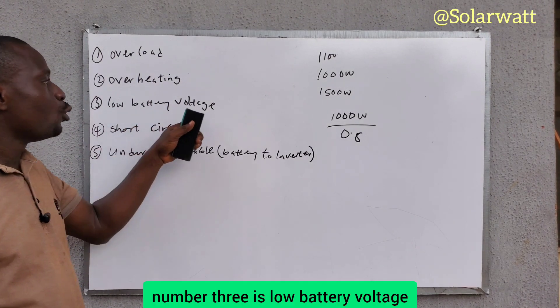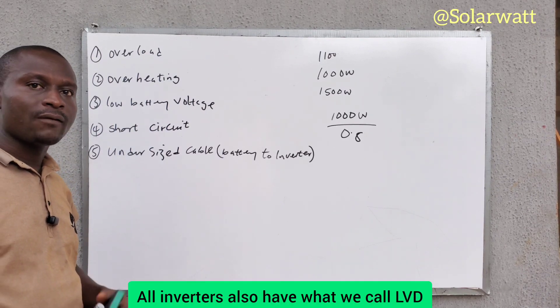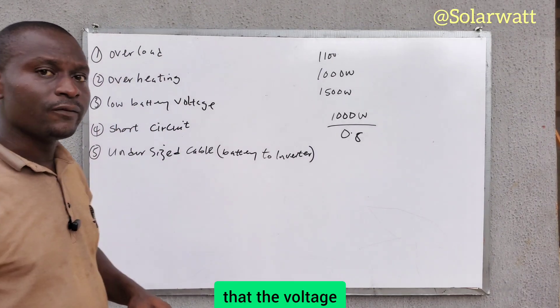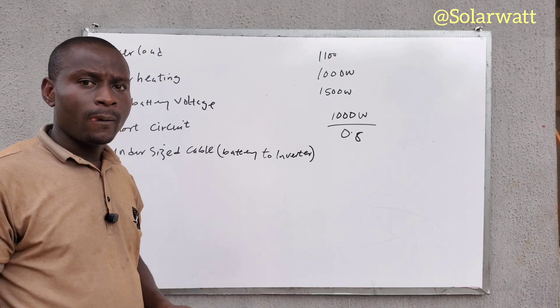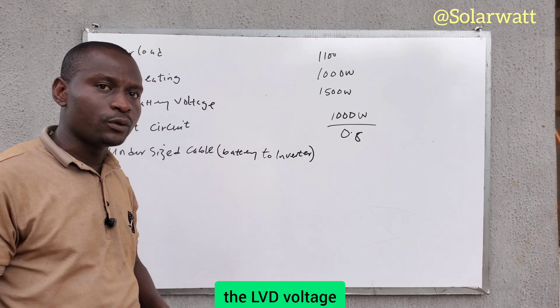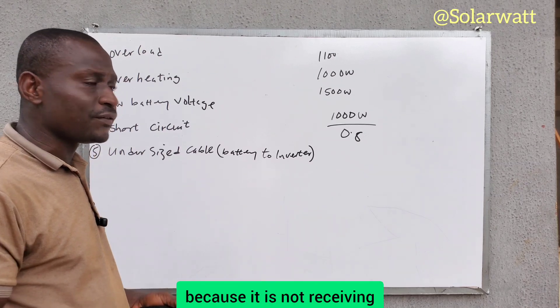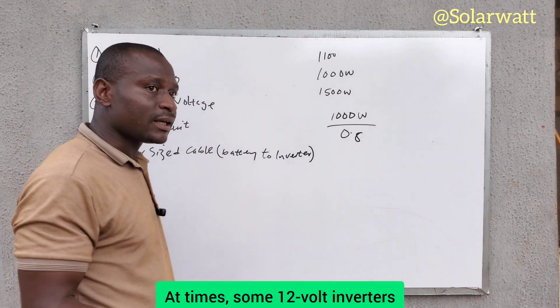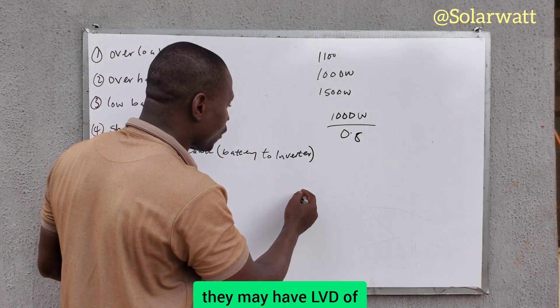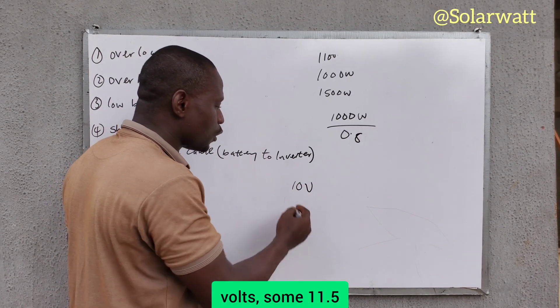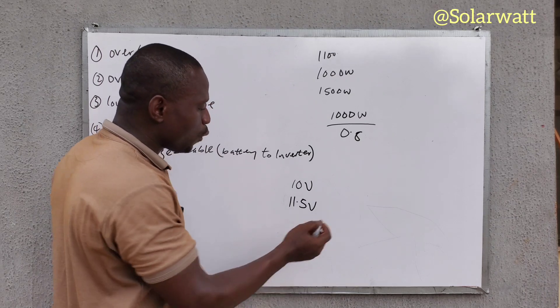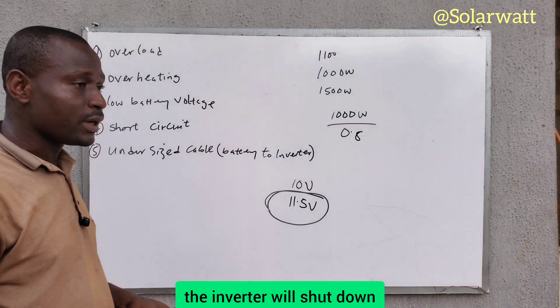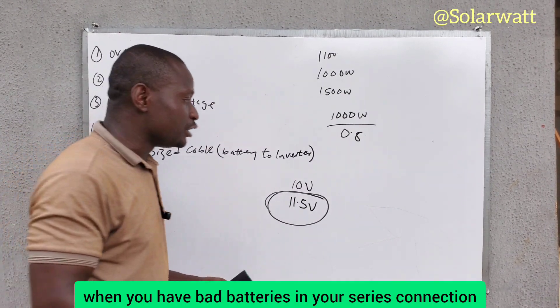Number three is low battery voltage. All inverters have what we call LVD — low voltage disconnect. Once the inverter senses that the input voltage from your battery bank has reached the LVD threshold, the inverter will shut down because it is not receiving the required voltage to operate efficiently. For example, some 12-volt inverters have an LVD of around 10 volts or 11.5 volts. Once the battery bank drops to 11.5 volts, the inverter will shut down. This often happens when you have a bad battery in a series connection.